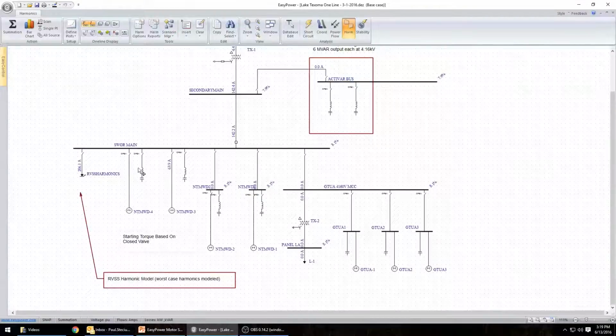So if I were to just turn on one of the capacitors associated with one of the starts, I would have a 14.3% distortion. You can see here that there's 207 amps of harmonic current flow into this capacitor branch. That certainly could result in fuse operation, and therefore I would investigate further. I can continue to do this type of analysis, clicking on various combinations that might exist.